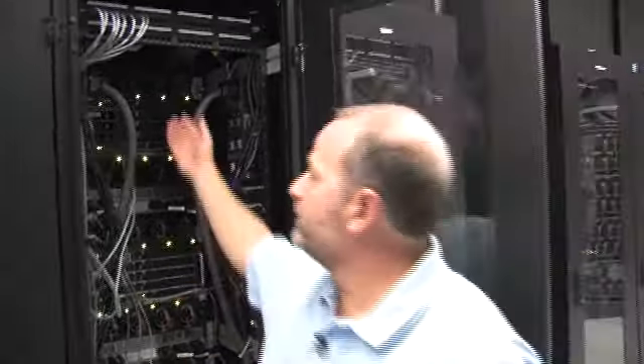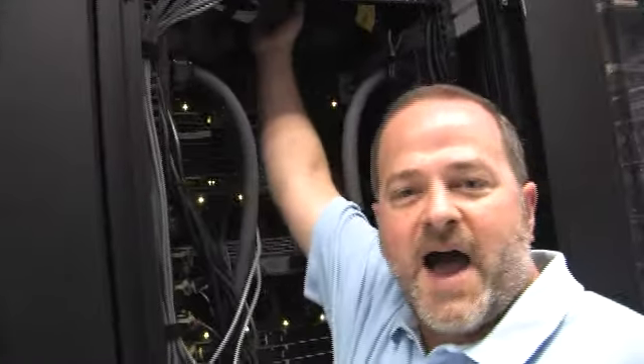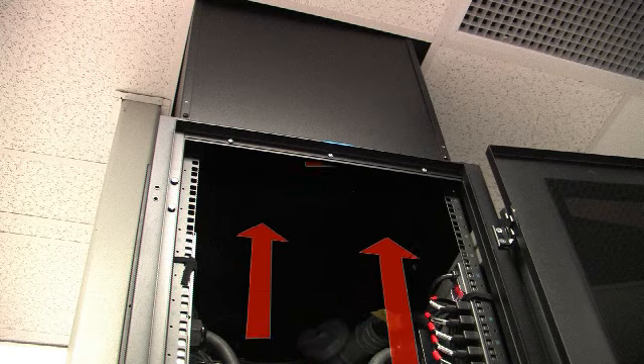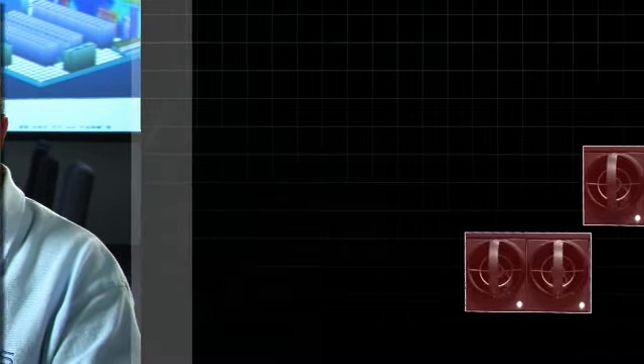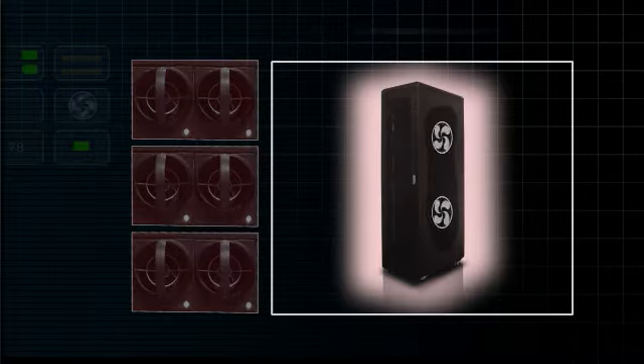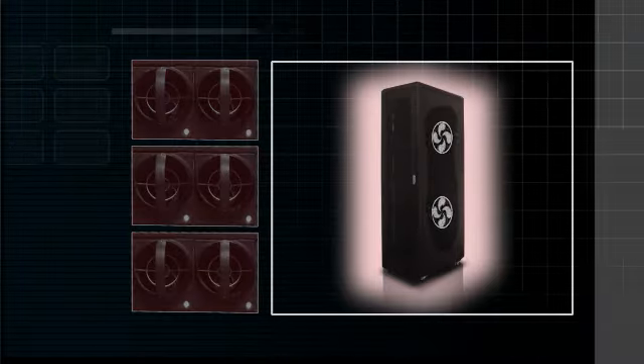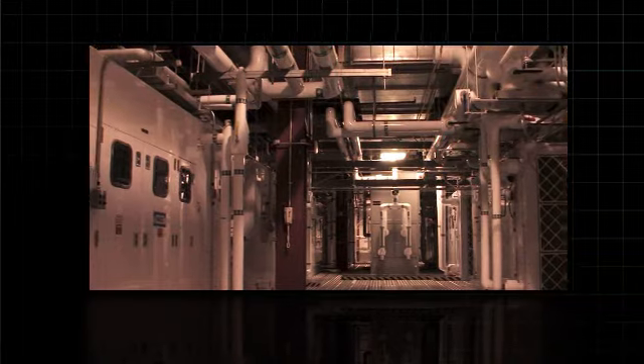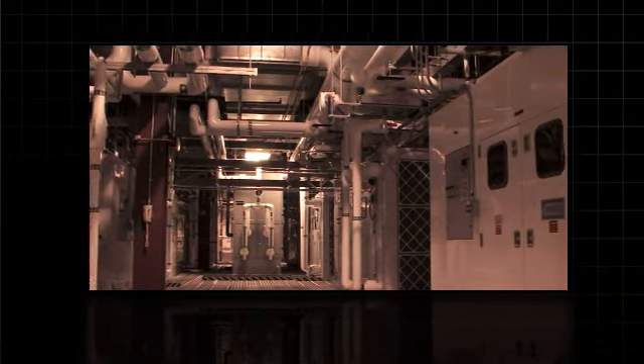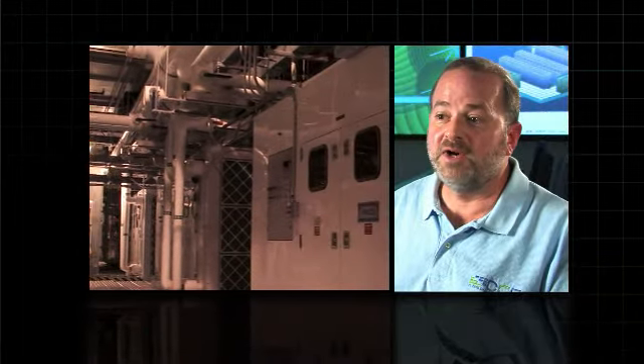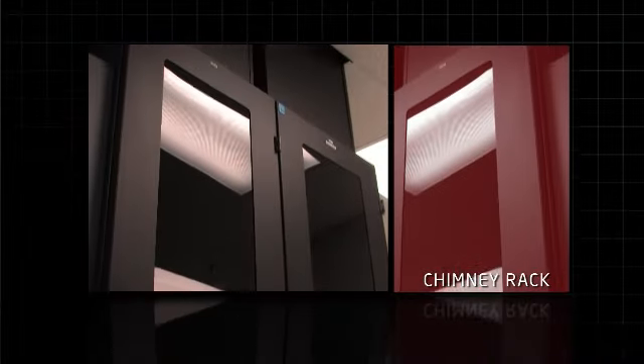The room is pressurized with cold air, and all the hot air goes up the chimney. By putting a chimney on the back of the rack and cleaning up the airflow obstructions in the rack, you're not relying on those little fans in the cabinet anymore, but on the big air handling units to move that air through. All that air goes directly through those racks in a very controlled fashion, because of the chimney rack.